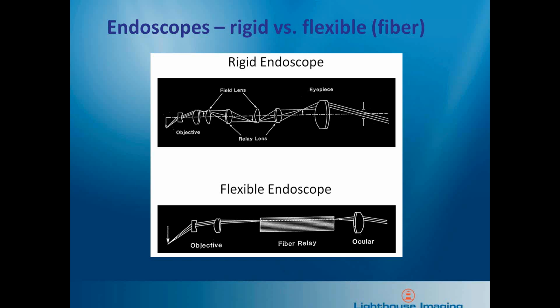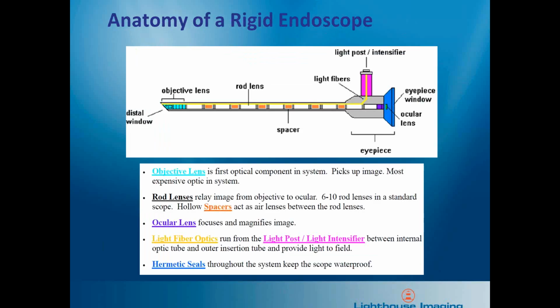So this is just a fairly basic slide discussing the flexible endoscopes, the fiber optic version of them. They would have an objective lens at the left end of the bottom image here, and then the image is actually relayed to the eyepiece or the ocular lens using fiber optics. And they are either fully flexible or semi-rigid is one of the more common ways to see that type of endoscope now. And we'll flip to the next slide, and we'll look at the more common version of construction of a rigid endoscope.